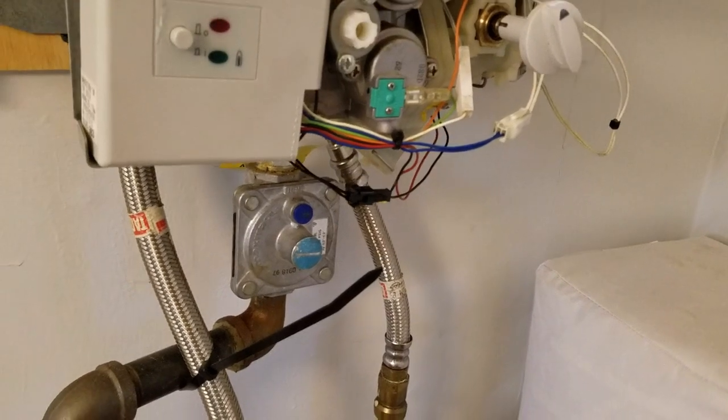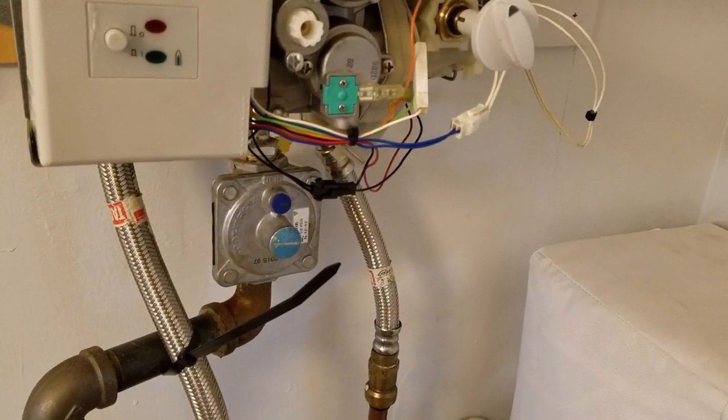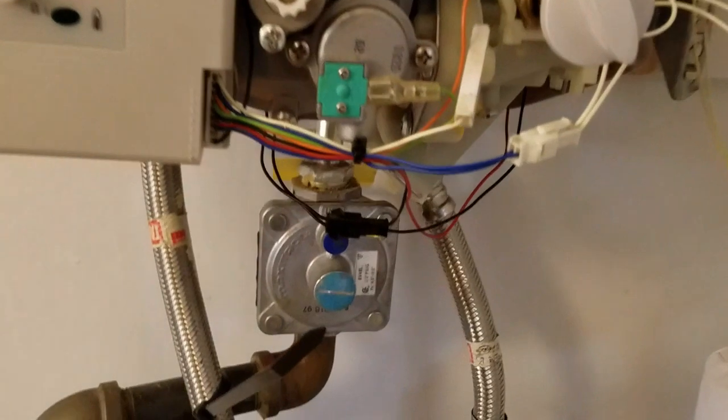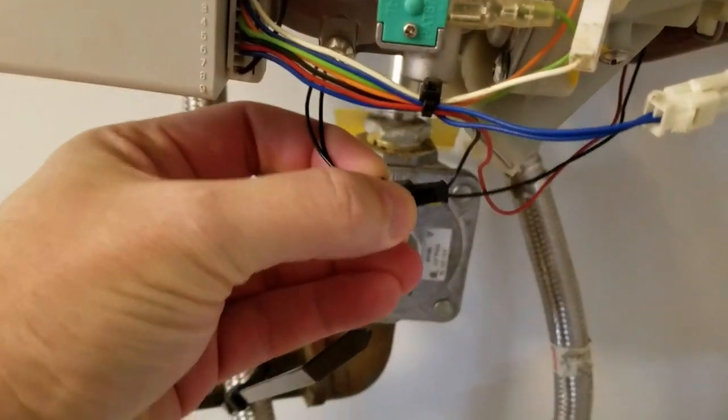So what you do to test - that's the actual mechanical switch for the water flow which turns on and off the gas valve. What you can do is if you unplug this little connector here.